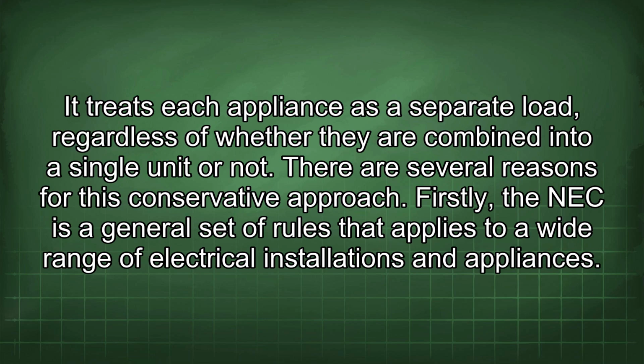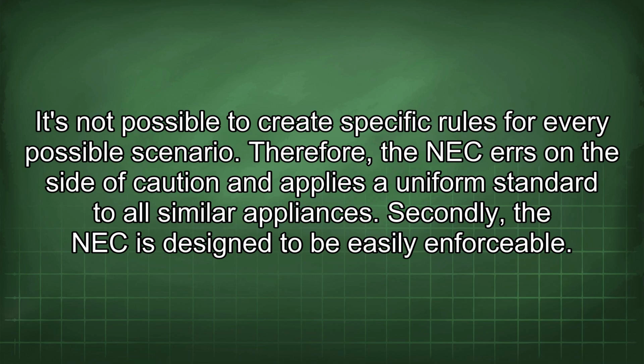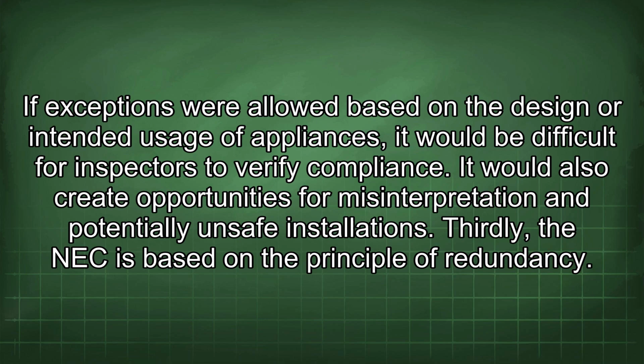There are several reasons for this conservative approach. Firstly, the NEC is a general set of rules that applies to a wide range of electrical installations and appliances. It's not possible to create specific rules for every possible scenario. Therefore, the NEC errs on the side of caution and applies a uniform standard to all similar appliances. Secondly, the NEC is designed to be easily enforceable. If exceptions were allowed based on the design or intended usage of appliances, it would be difficult for inspectors to verify compliance. It would also create opportunities for misinterpretation and potentially unsafe installations.